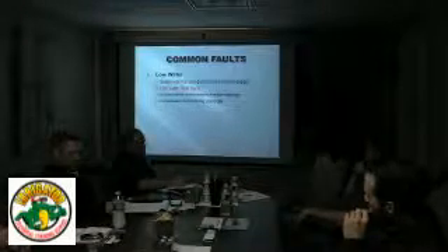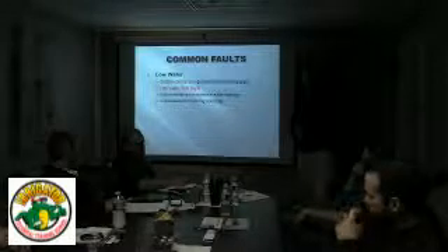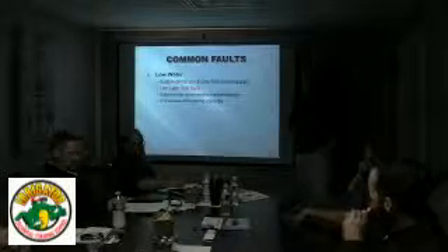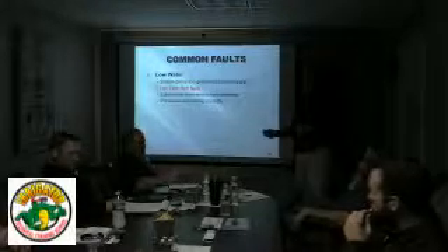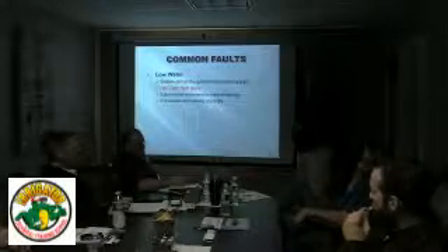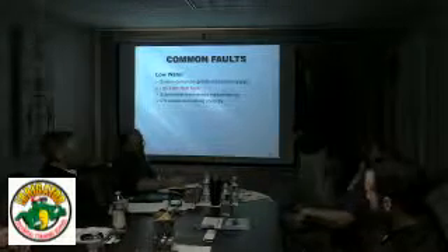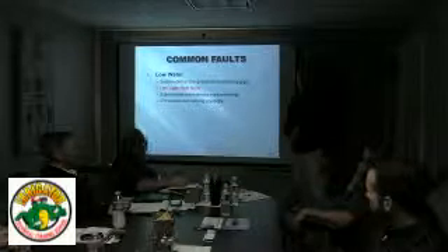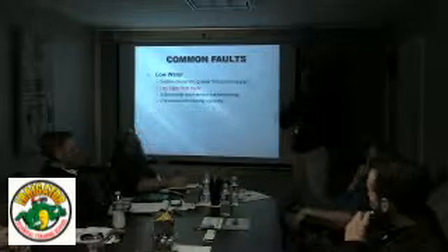Low water float is faulty. We either use a level sensor in the vault or a float switch. It's just a bulb with a weight on it that floats. Occasionally I see those where the incoming water is causing turbulence, and so it's sat there and rubbed up against a concrete vault for several years and worn right through it. I've also seen some that have been in so many years that the cord gets so stiff that it just won't bend back down. Cracks.